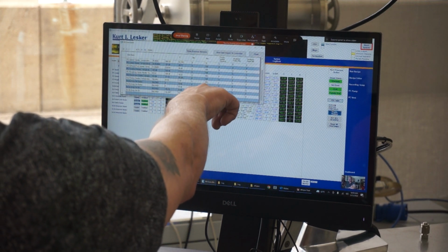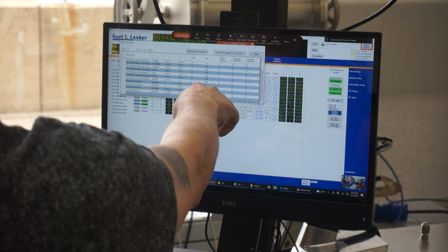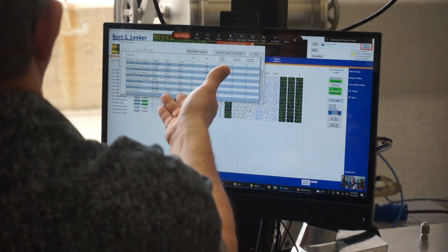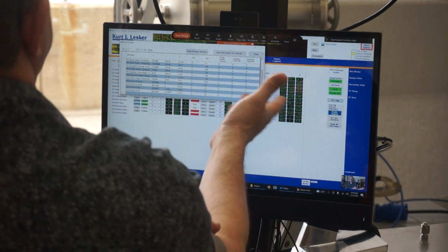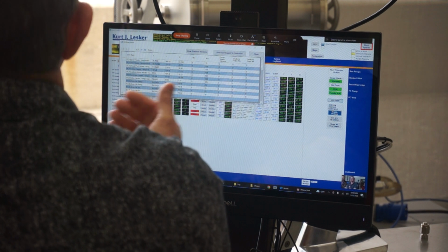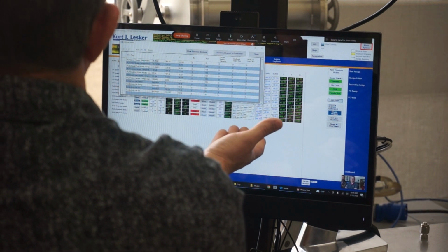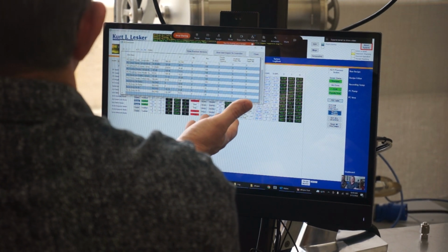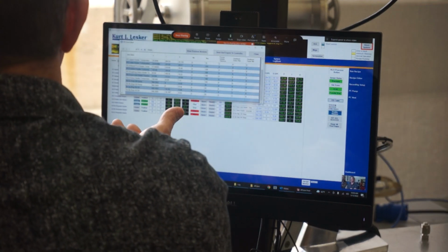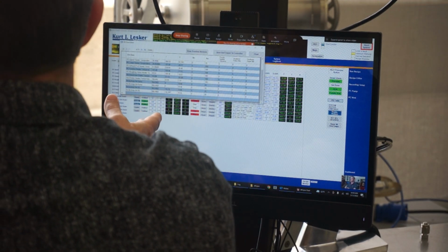And then we just have this as a ceiling, acting as a buffer. You can input any PID values you want, but this is set up for normal operation, what most people use. More so you're aware that it's there. If you get into running something other than zirconium, then maybe we might change the PID values.